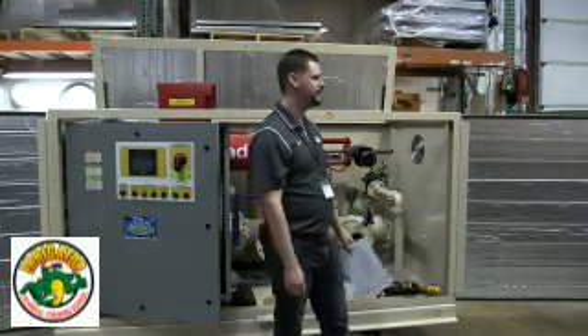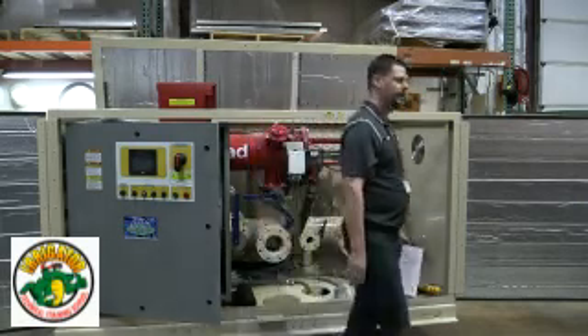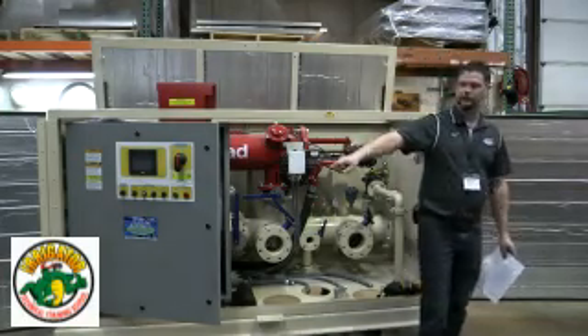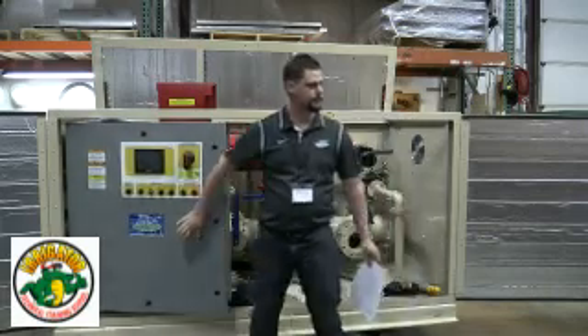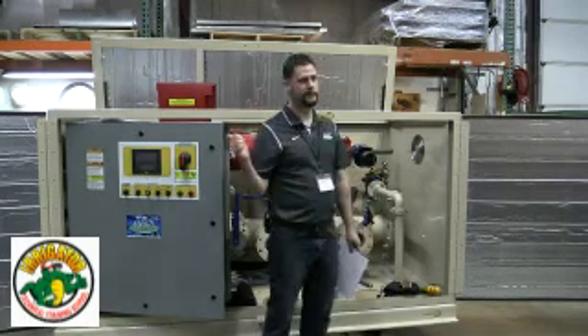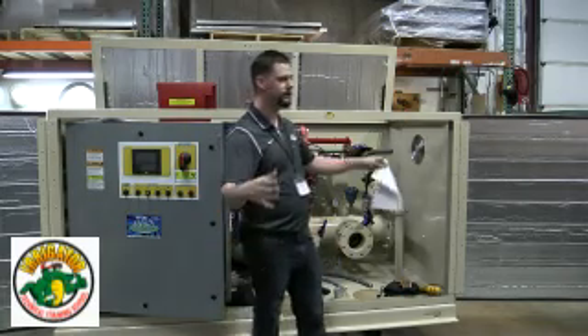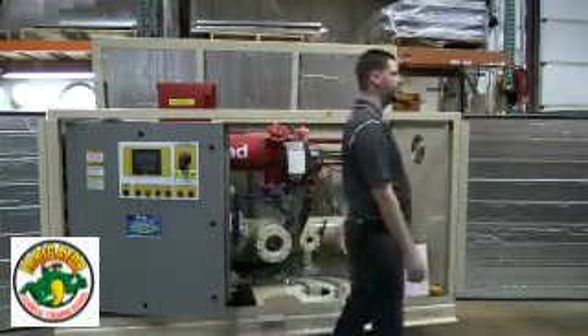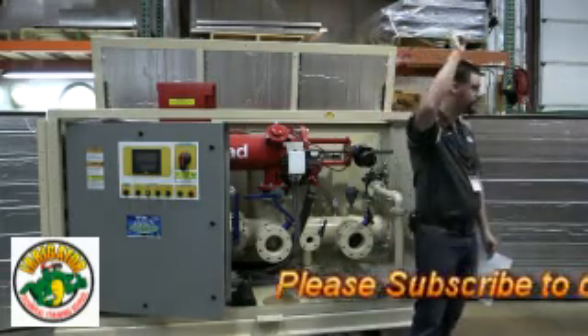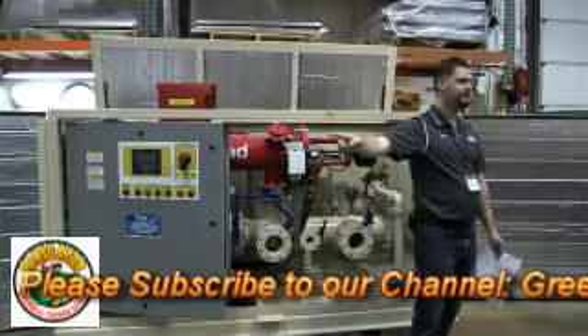But, and I know we talked about this yesterday, so you guys get a more in-depth overview. At very least, you want to know for sure that there's water going out to it. Now, almost all of our systems are programmed to open that valve when the main pump is running. So if you only have a pony pump running, it's not going to open that valve. The assumption is that there's not enough water going through that screen to worry about it clogging. Also, the pony pump probably produces just a little bit more than the screen is going to take. So it wouldn't make sense to run it anyway.